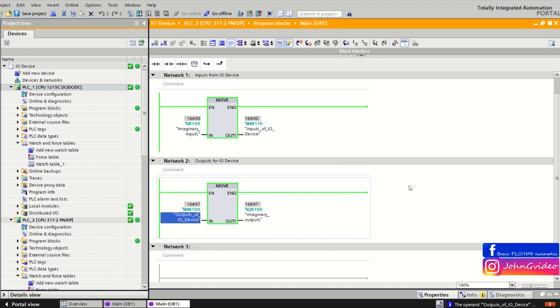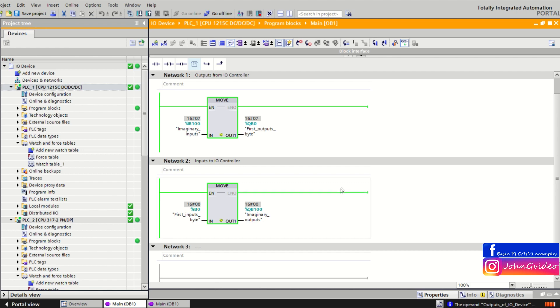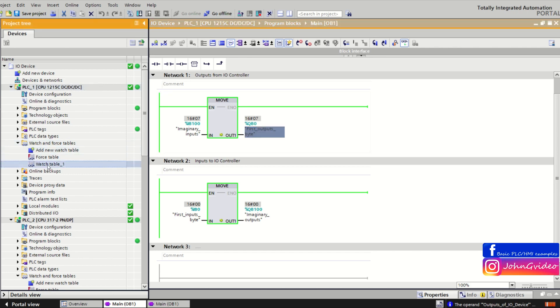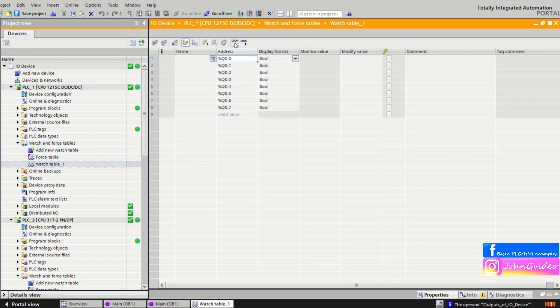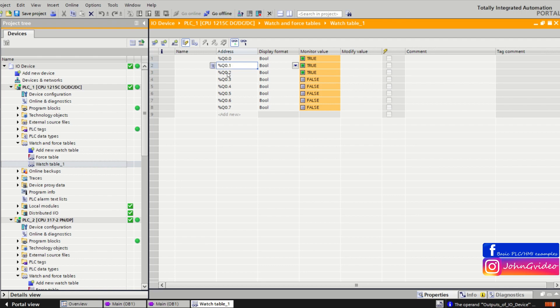We set the output of the IO device variable. We use hex number seven. This means we move this information to the imaginary output. This output is received by the IO device on the imaginary input, and moved to the hardware output of the IO device. Now we check by the watch table if we receive this information and we set the hardware output of the IO device to true.